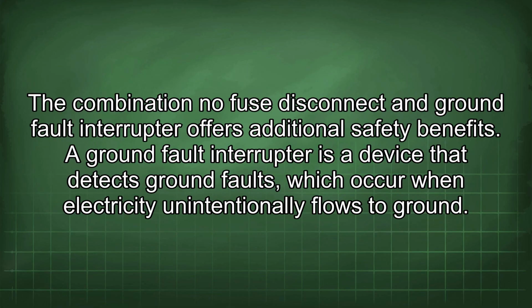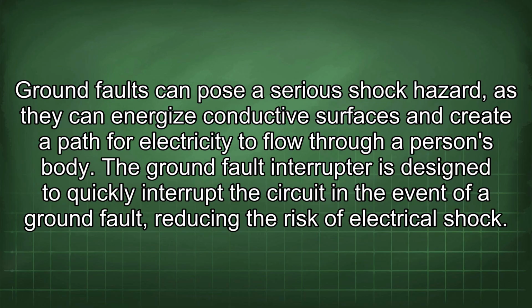The combination no fuse disconnect and ground fault interrupter offers additional safety benefits. A ground fault interrupter is a device that detects ground faults, which occur when electricity unintentionally flows to ground. Ground faults can pose a serious shock hazard, as they can energize conductive surfaces and create a path for electricity to flow through a person's body. The ground fault interrupter is designed to quickly interrupt the circuit in the event of a ground fault, reducing the risk of electrical shock.